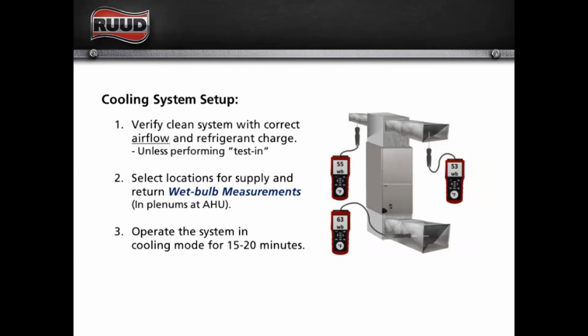So you're going to set up your cooling system. You're going to operate the system in cooling mode, and you want to allow it to run long enough so that we start pulling moisture out of the air. This says operate in cooling mode for 15 to 20 minutes. I would say, I like 30 minutes is a good standard. I like 30 minutes. So allow the system to run for a while. While it's running, you can check your static pressure. You can convert that to CFM. You got your CFM.